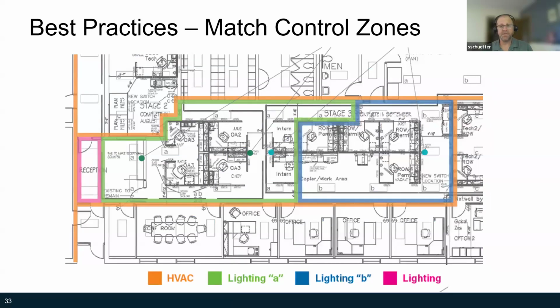In the lighting and control design step, attention should be paid to the coordination of the HVAC and lighting zones. HVAC zones are largely driven by existing HVAC system design and thermostat or terminal unit locations. Lighting control zones are usually based on luminaire and lighting control locations, as well as space usage needs. The coordination goal is to align lighting zones with existing HVAC control zones as best as possible.